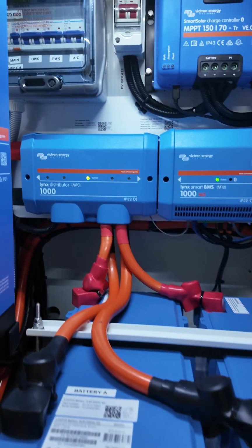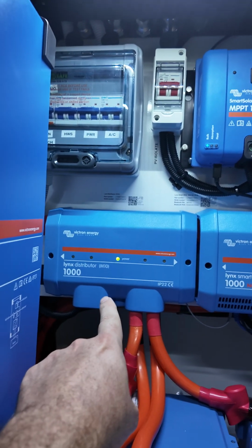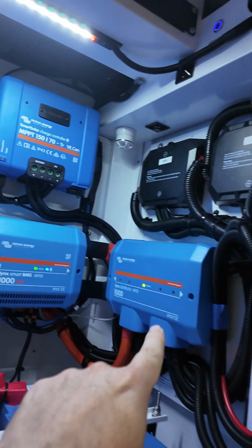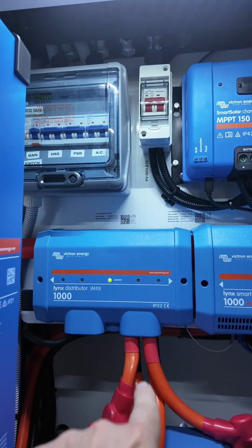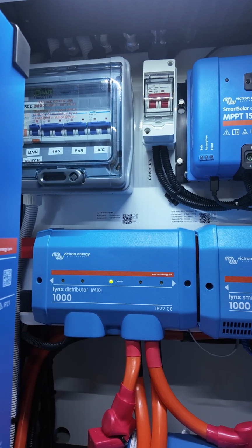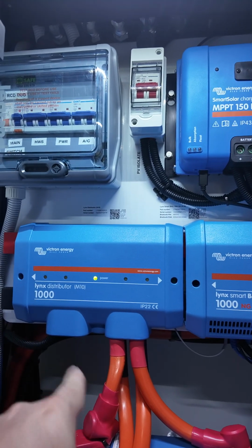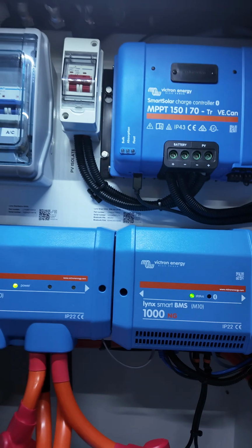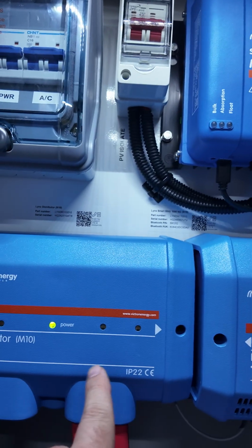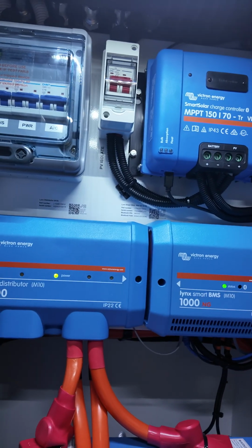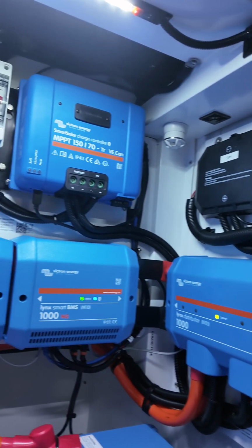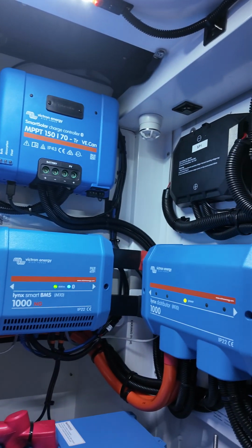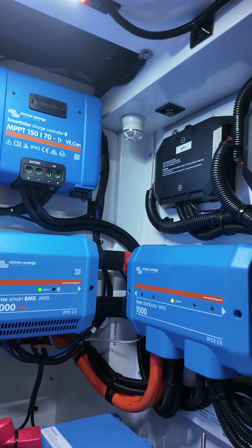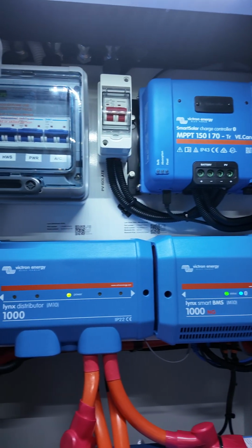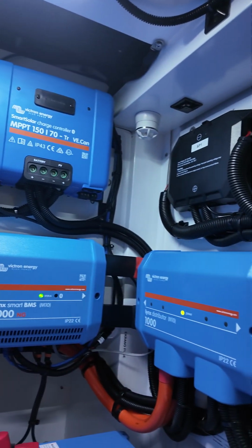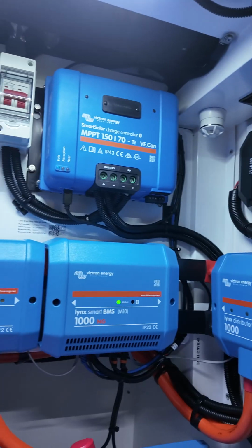They run through to the main bus. This first distributor here, and there's a BMS and another distributor there, but the first distributor is the battery distributor. You'll see the cabling runs up into that distributor. There's room for more connections there, but each distributor has 4, and each of them are fused. If there's a failure, the light will indicate on one of the connections. The main purpose of the distributor is to create an electrical backbone or highway for the distribution of current through the system. This is a very high current system, hence we use distributors and not normal bus bars - these are 1000 amp rated. So that's the battery distributor.